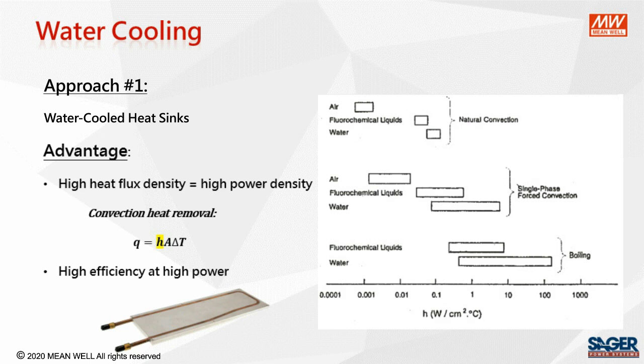If we review the convection heat transfer formula, remember that the heat transfer coefficient, H, depends on various factors, such as velocity and viscosity of the surrounding fluid or air. By using water cooling, we're increasing the heat transfer coefficient because water gives us a higher heat transfer coefficient than air. We're resorting back to forced convection, like in fan cooling, but instead of air, we're using water.